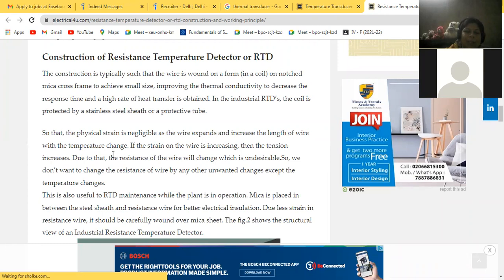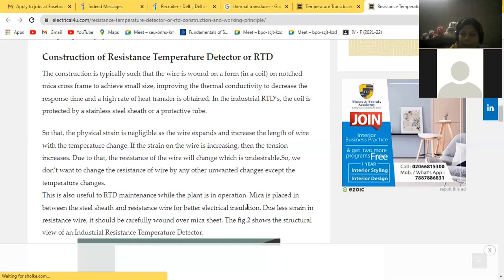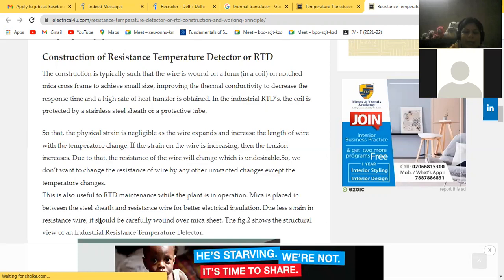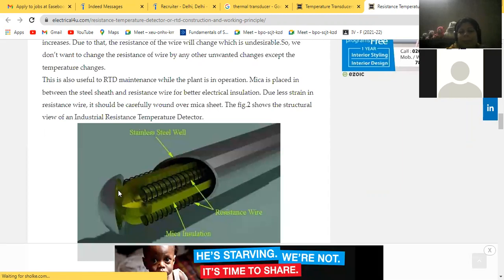If the strain on the wire increases, then the tension increases. Due to that, the resistance of the wire will change, which is undesirable. So we don't want to change the resistance of the wire by any unwanted changes except the temperature change. Now this is also useful for RTD maintenance while the plant is in operation. Mica is placed in between the steel sheath and resistance wire for better electrical insulation. Due to less strain on the resistance wire, it should be carefully wound over the mica sheet. Now you can see here. अभी हमने पीछे भी देखा है, same diagram. Stainless steel sheath, resistance wire, and mica insulation is there.